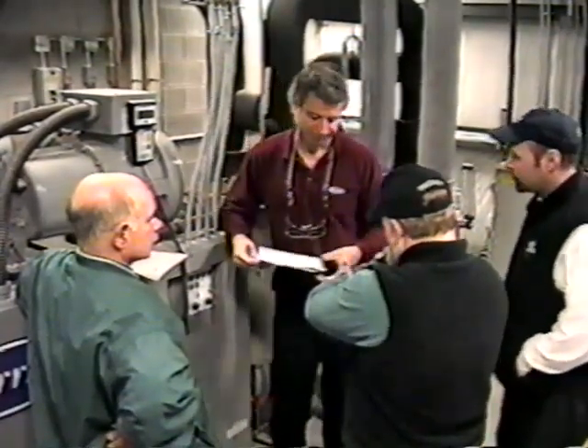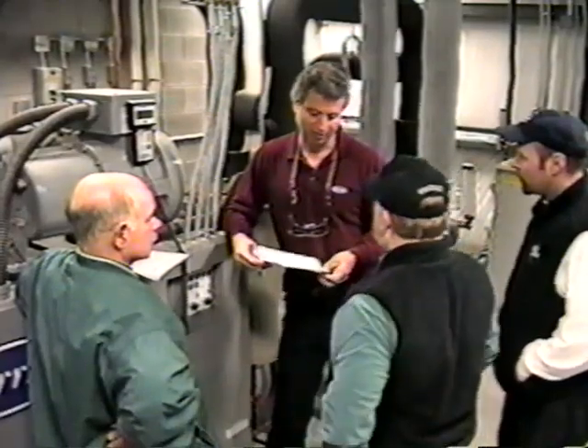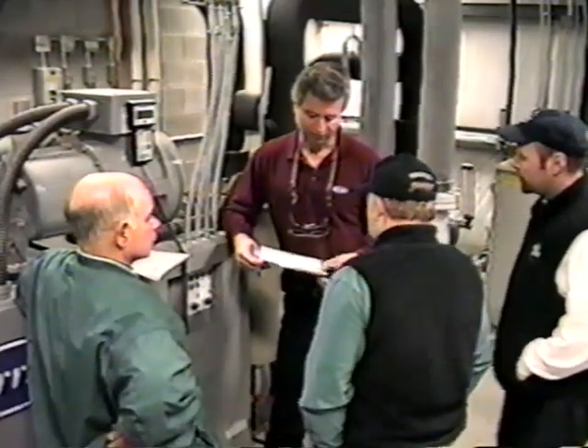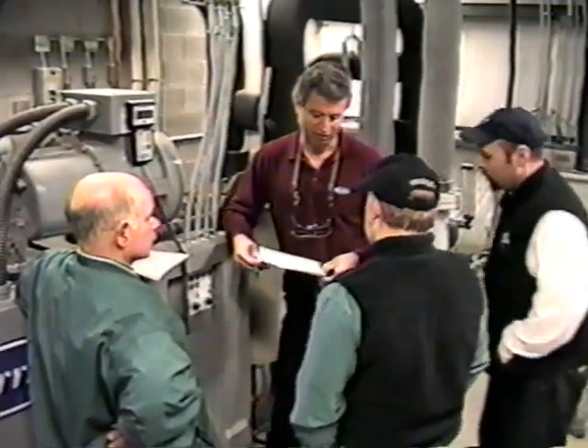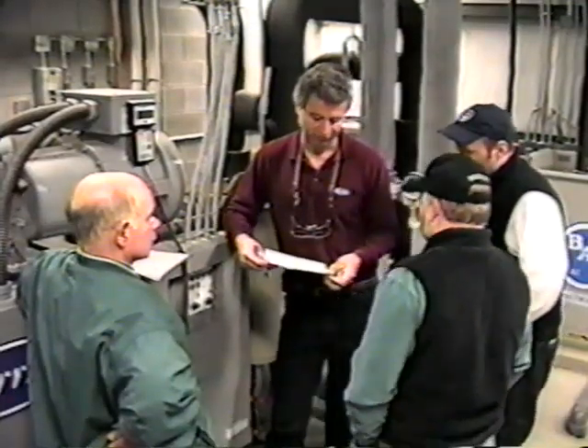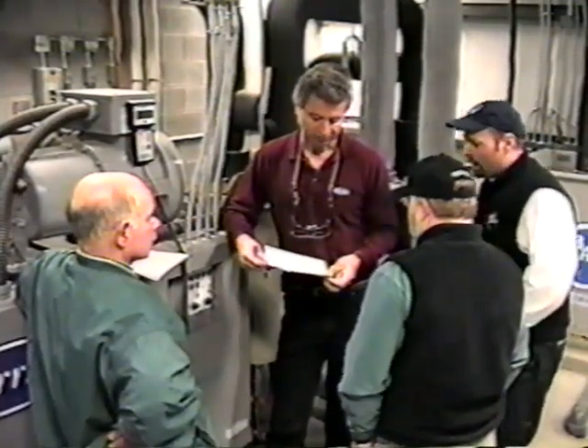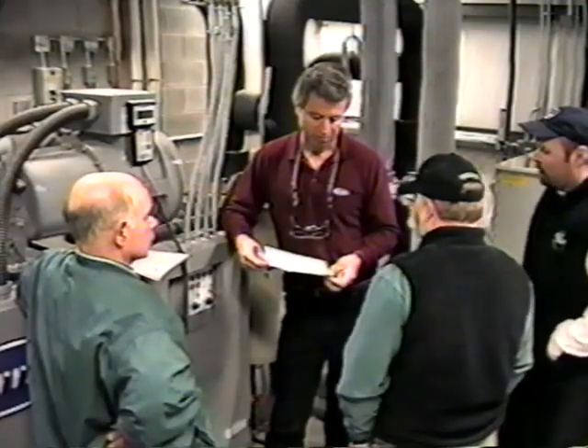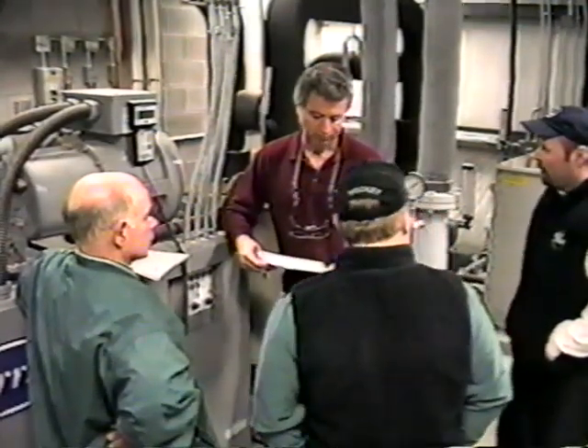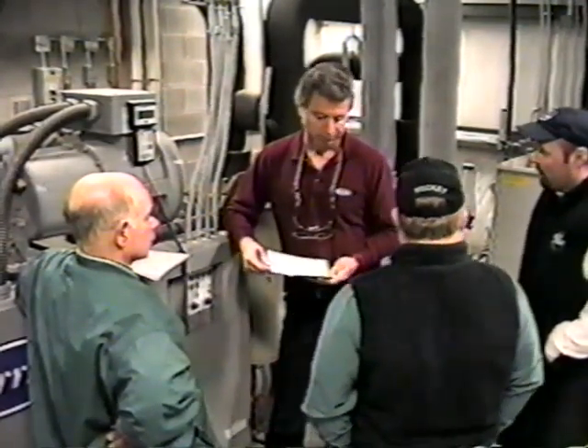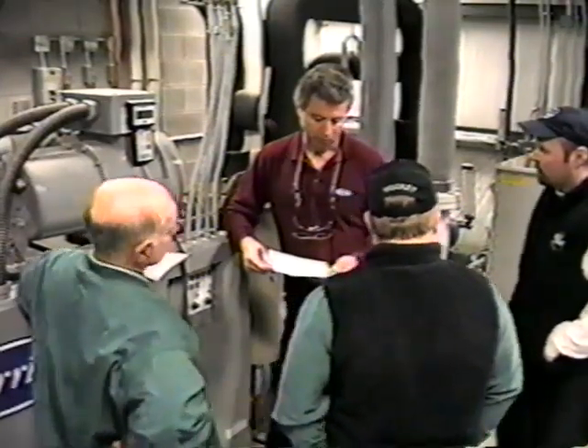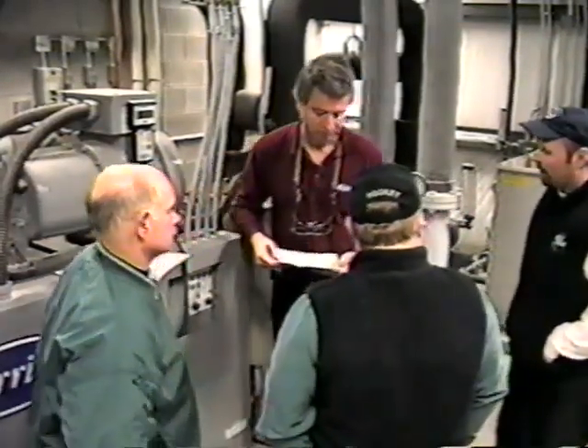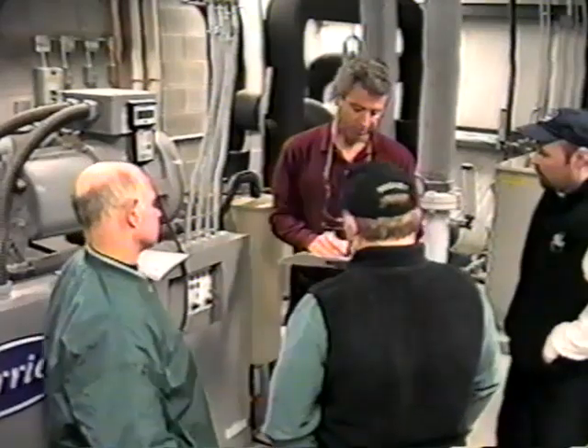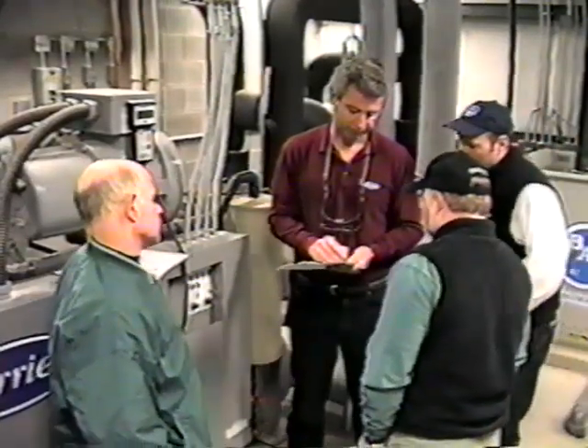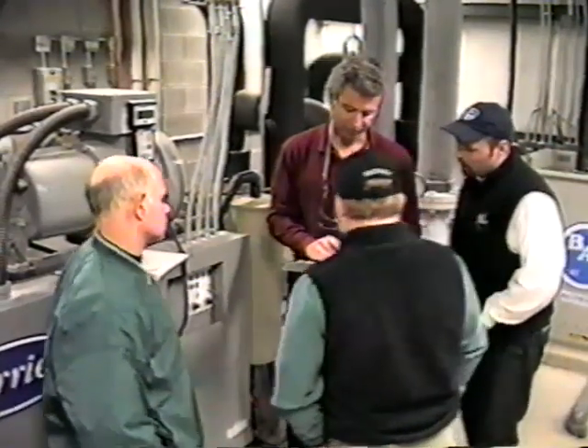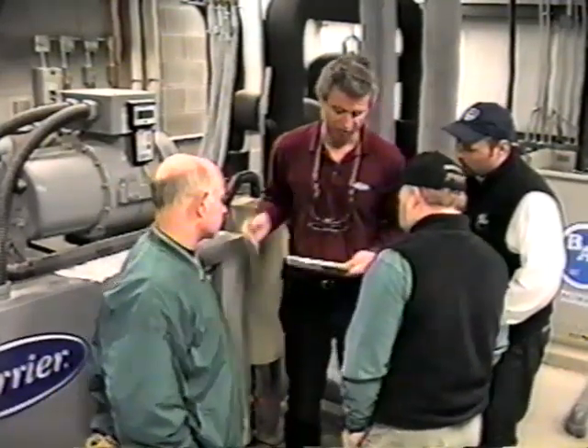Your pressures, other than maybe once in a while, I wouldn't take those every time. I don't think it's necessary unless you feel up to it. Over there, we take suction, discharge and oil pressure all the time. After a couple of months, half my time goes to the low running hours, to see how long those are. Don't worry about calculated oil pressure, that's just a calculation process.